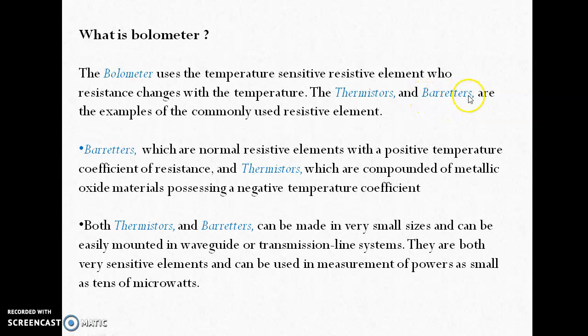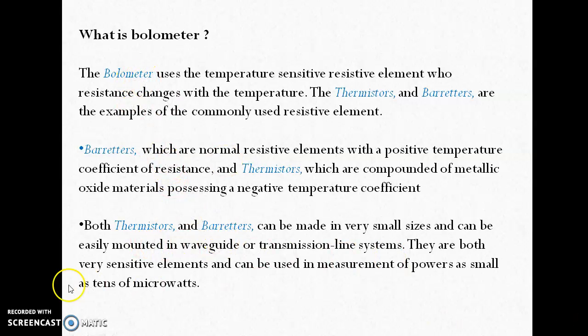The thermistor and barretter are elements made of different metals and have different sensitivity, in the sense that the change in resistance caused by a power change is different in the thermistor and the barretter. Both can be made in very small sizes and can be easily mounted inside transmission line systems, which is why they are used as bolometer elements. They can measure power as low as tens of microwatts.